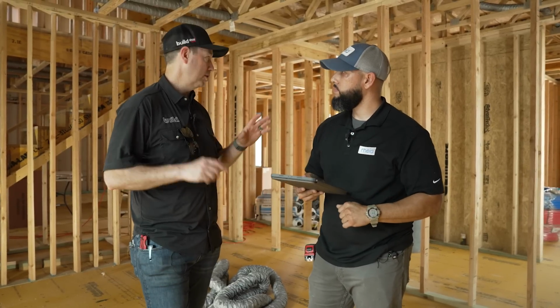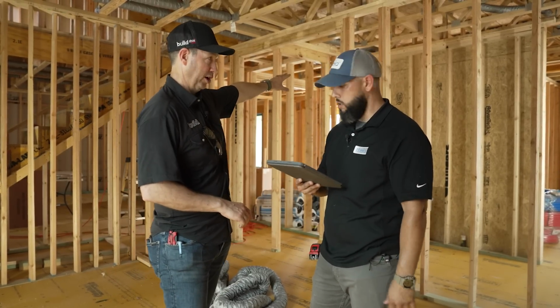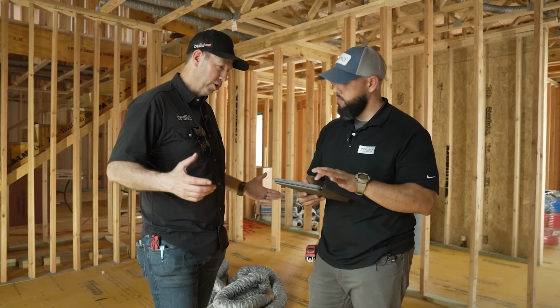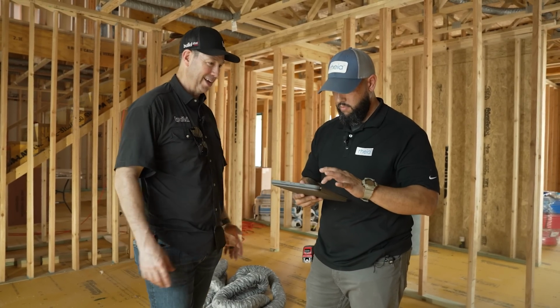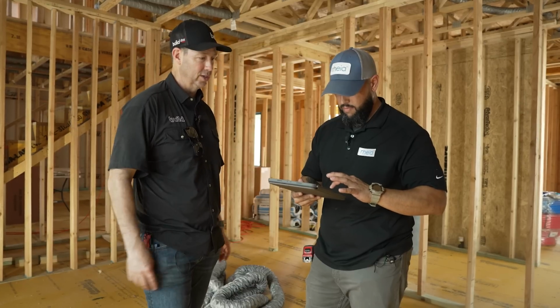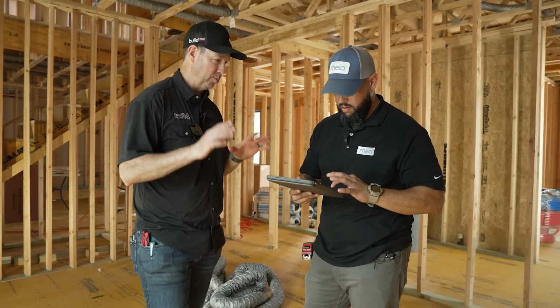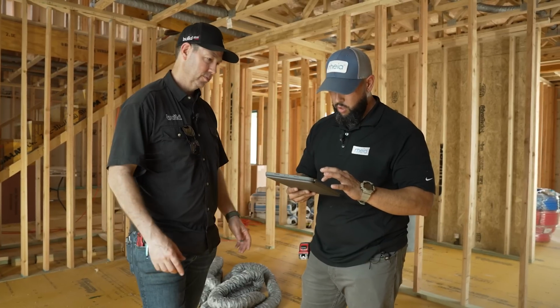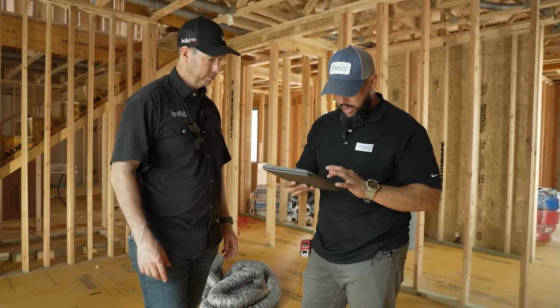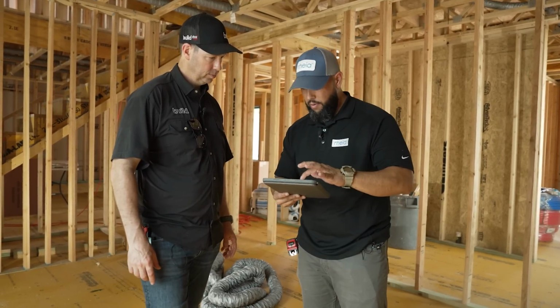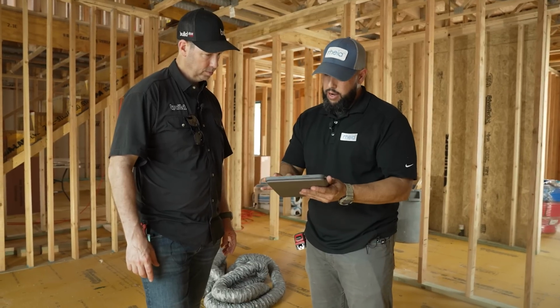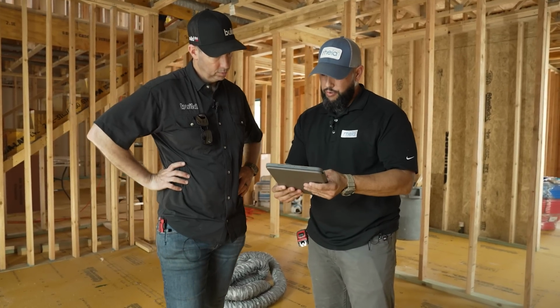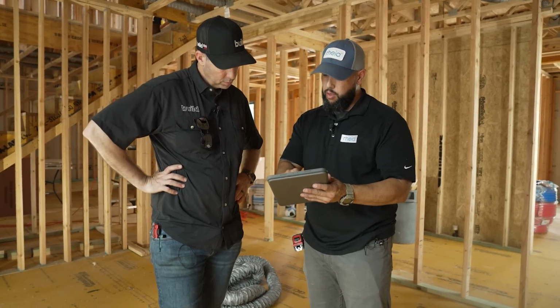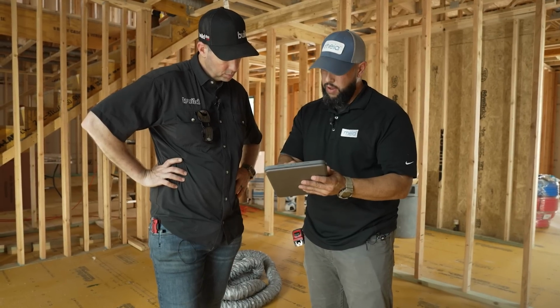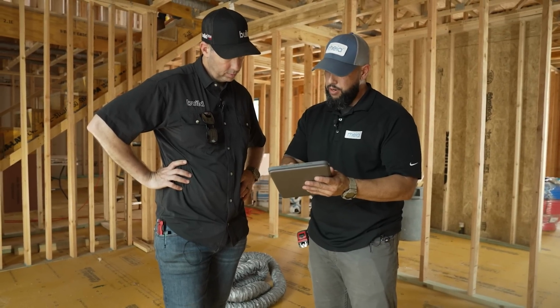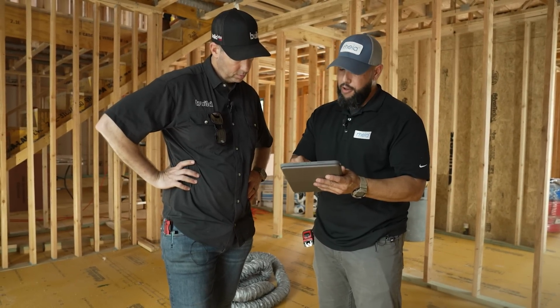Okay, so let's use, for instance, maybe this den on the first floor here, which is a guest room or maybe a home office. We called it a den on the plans. Let's use that as a for instance. Talk to me about what the program's spitting out for that room. All right, so what the program will spit out for that room is a design calc file. And in this design calc file right here, you're gonna see your velocities. So for the den, for instance, we can see right here that we have 35 expected CFM on that run at a 4-inch diameter duct, and that's 386 feet per minute.